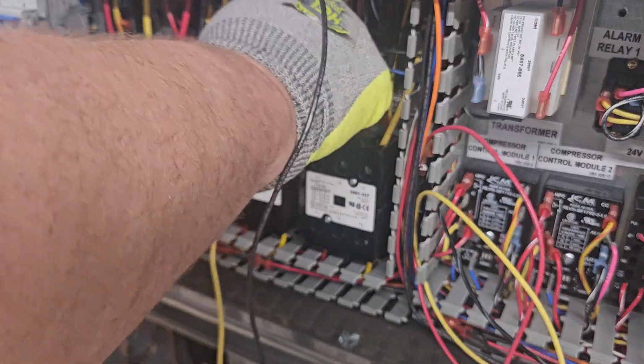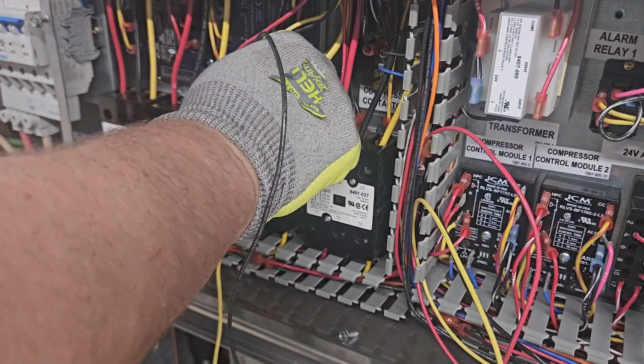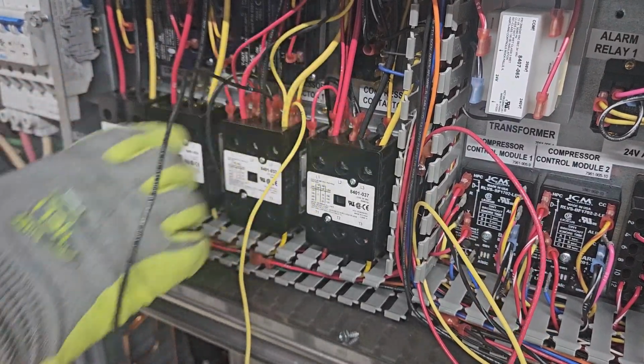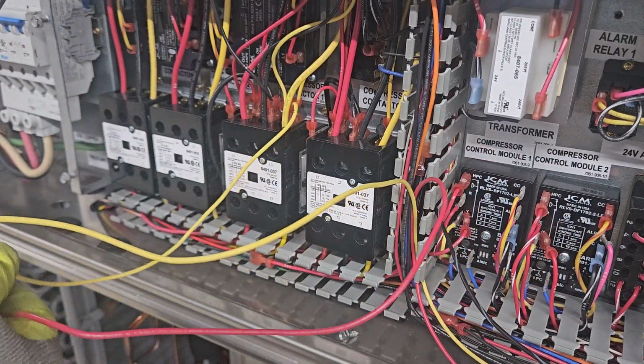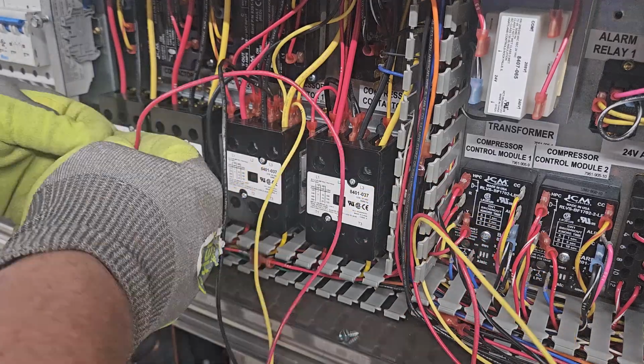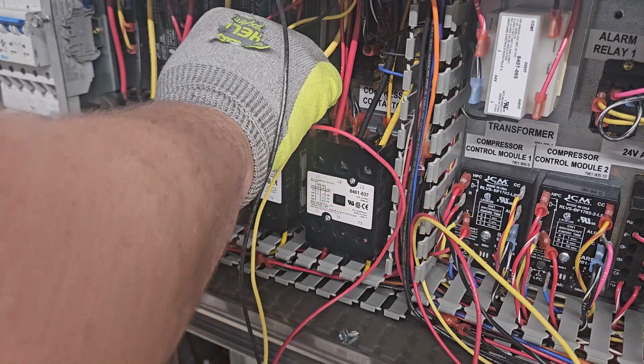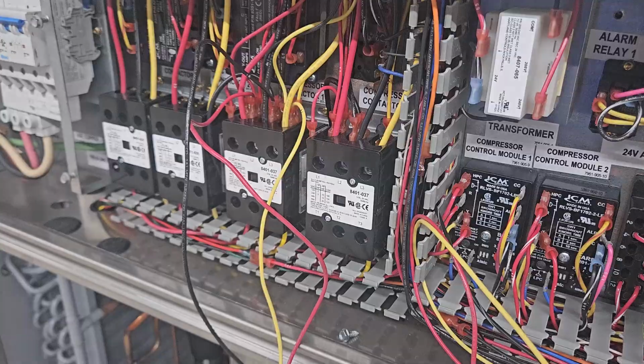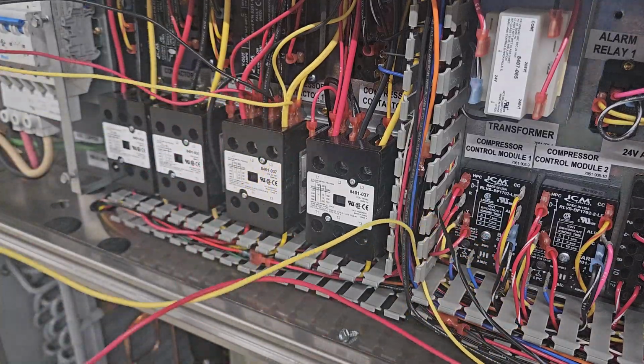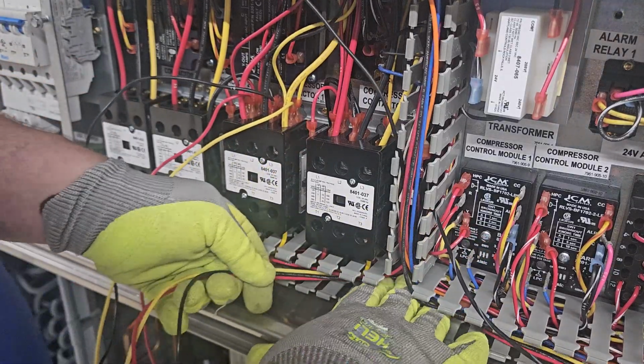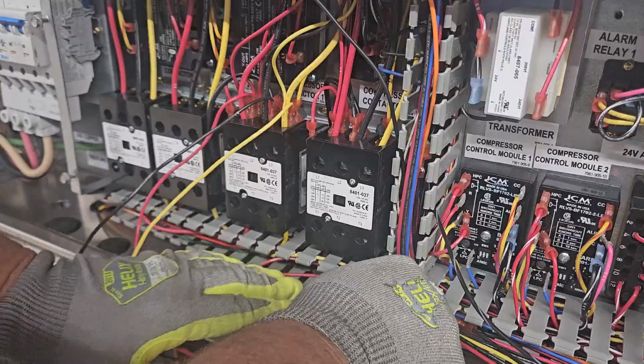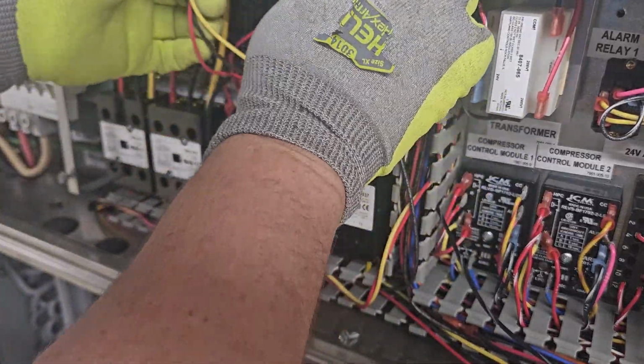At the contactor, hook the red wire to L1, the black wire to L2, and the yellow or blue wire to L3, matching what was seen at the condenser fan motor. After connecting the motor power wires to the line side of the contactor, position the wires in the channel chase and install the channel covers to the wire chase.